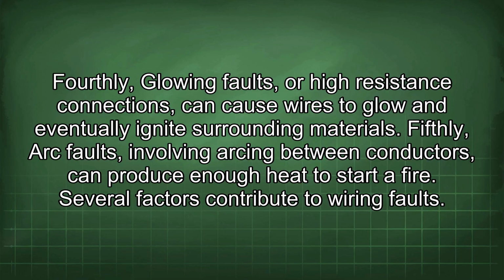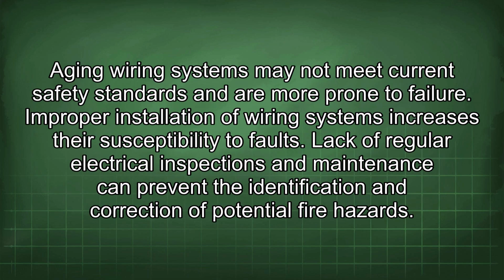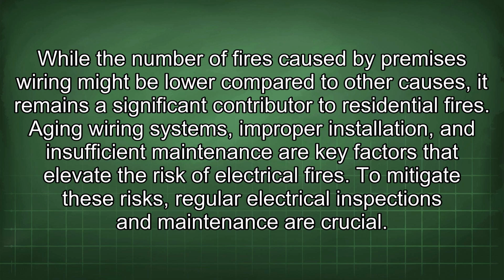Several factors contribute to wiring faults. Aging wiring systems may not meet current safety standards and are more prone to failure. Improper installation of wiring systems increases their susceptibility to faults. Lack of regular electrical inspections and maintenance can prevent the identification and correction of potential fire hazards. While the number of fires caused by premises wiring might be lower compared to other causes, it remains a significant contributor to residential fires.